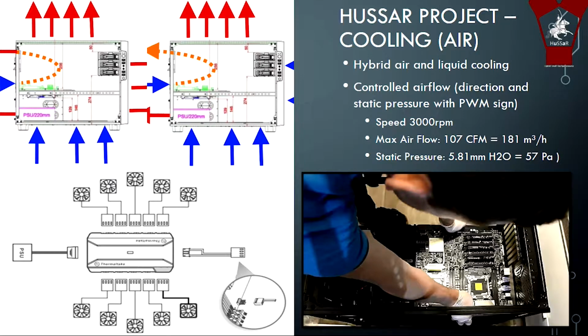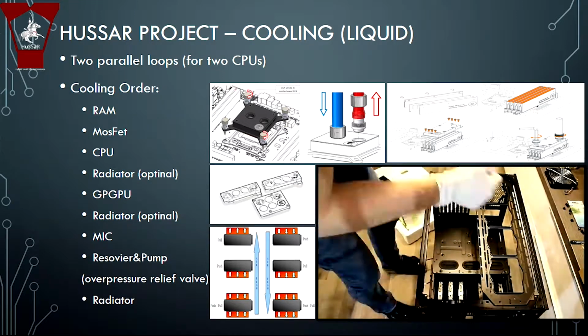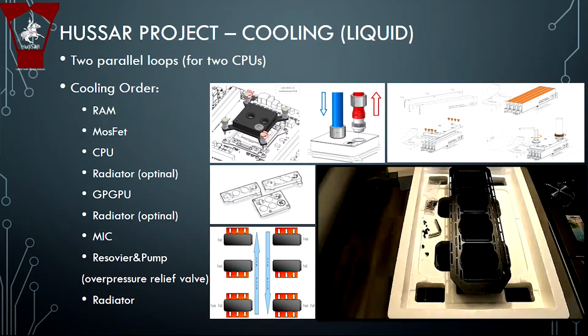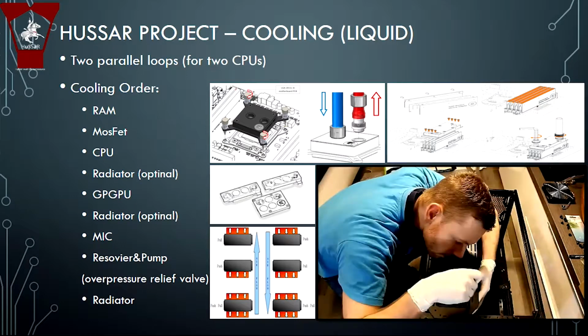There are some interesting numbers. We use very high performance ventilators. The speed is 3000 RPM, and the static pressure is almost 60 Pascal. Of course, it can't work all the time at full capacity, but if it is necessary, it can.